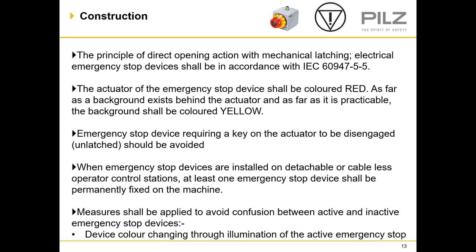Moving on to the construction of emergency stops and the principle of direct opening action with mechanical latching. Electrical emergency stop devices shall be manufactured in accordance with IEC 60947 part 5. The actuator of the emergency stop shall be coloured red, and the background behind the actuator shall be coloured yellow. The actuation of the emergency stop contacts should be made through a rigid member which directly affects the contacts. Emergency stop devices requiring a key to be disengaged or unlatched should be avoided, as these could be a source of injury to the hand of the operator.